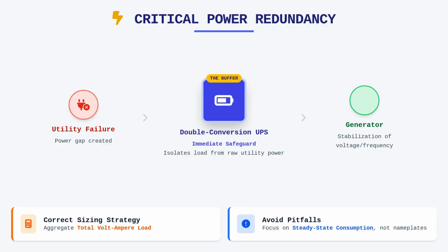Instead, you should focus on the steady-state power consumption while accounting for the maximum possible power factor of the connected load. A double conversion online UPS is the industry standard for mission-critical facilities because it isolates the load from raw utility power entirely, effectively creating a clean power environment regardless of input disturbances.